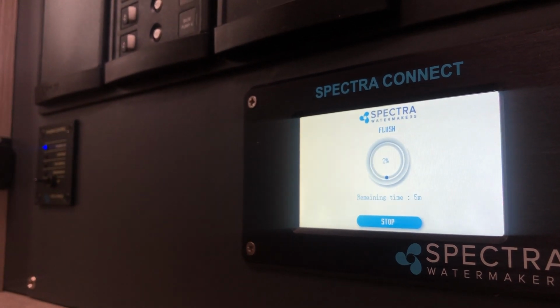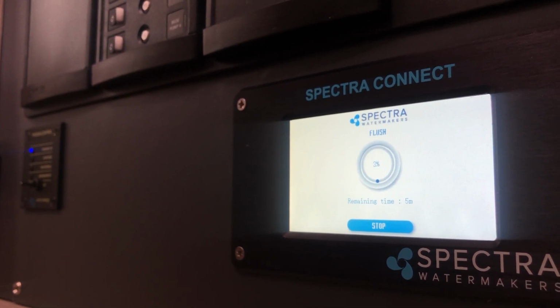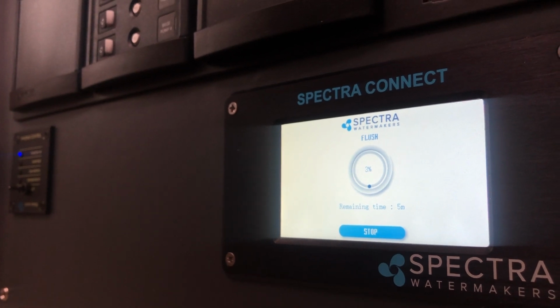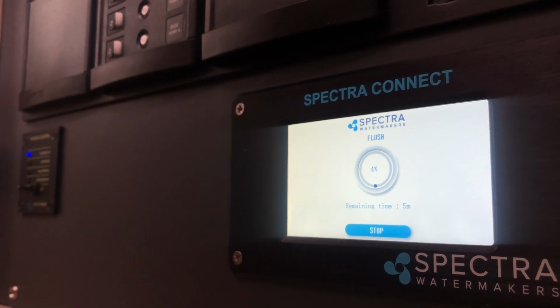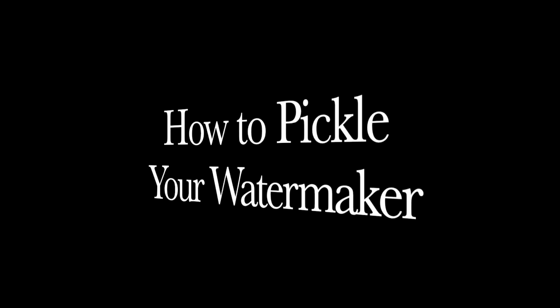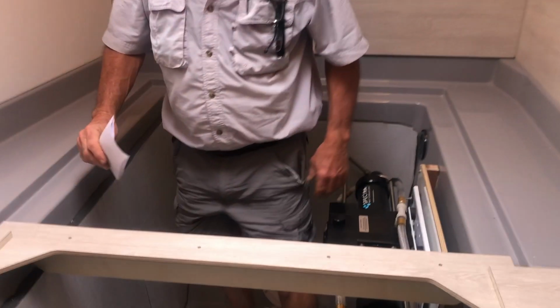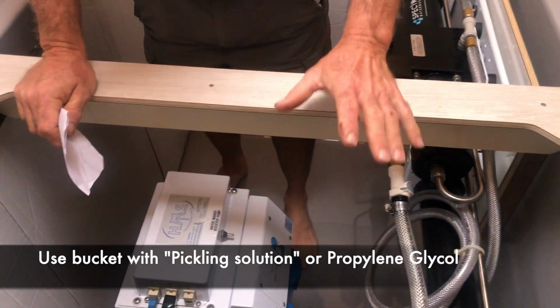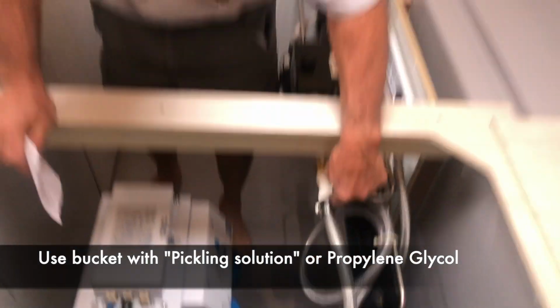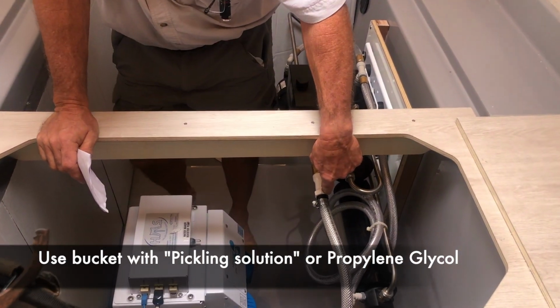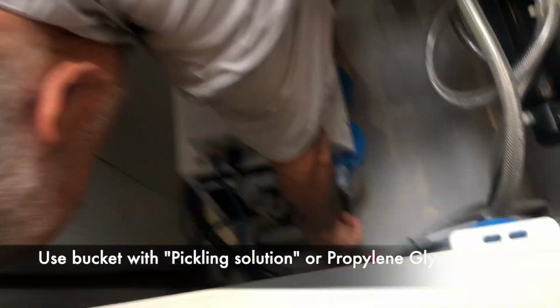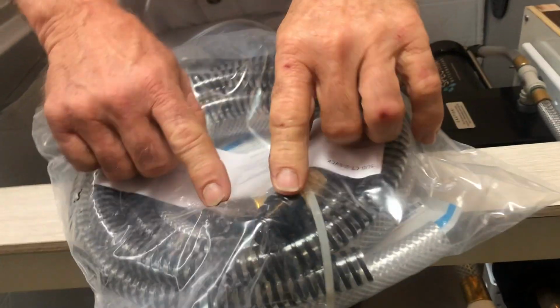You're doing good. That's nice. And that flush is just going to go like that for 5 minutes. Put the 2 gallons of propylene glycol in it. Set it right where I had mine set. Quick disconnect fitting here. Okay, there's another quick disconnect fitting right down here. You see they have the 2 quick disconnect fittings.